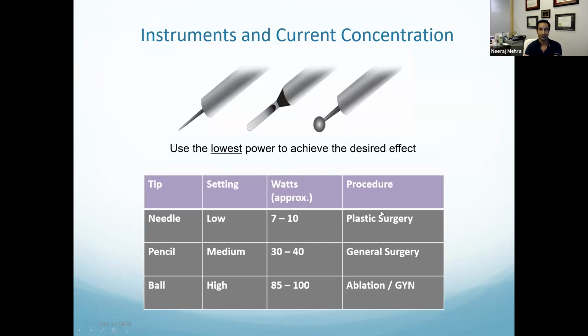You'll notice that with different types of surgery, they use different energy settings, and that really has to do with your current density. If you're working in a really fine area — say vulvar surgery — you don't want a lot of extra tissue or thermal spread, so you want a low energy setting because you have a high current density. A high current density means you want a low energy setting to get the desired effect without excess.